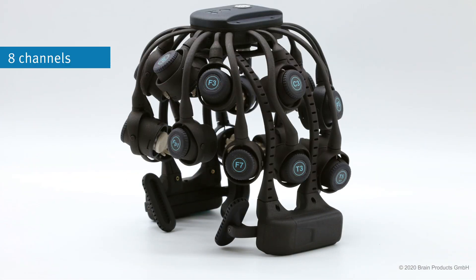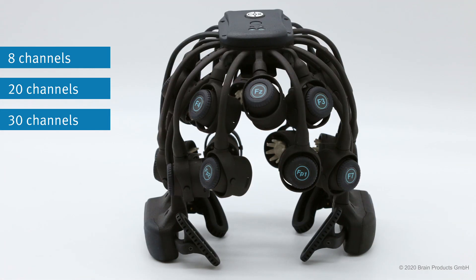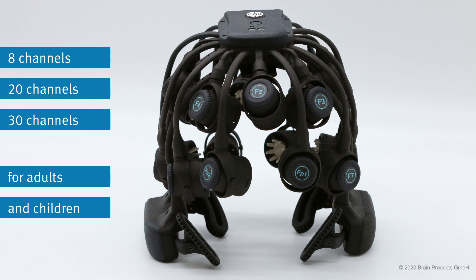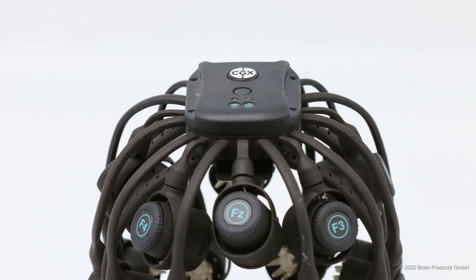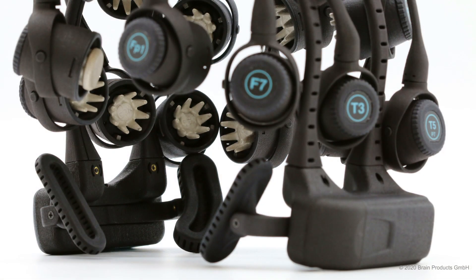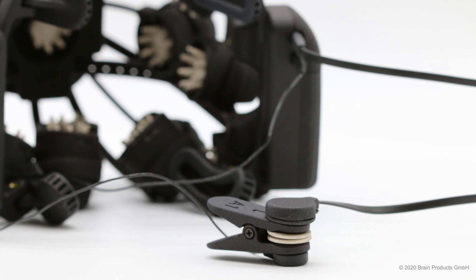The Quick headset comes in 8, 20, or 30 channel configurations and follows the one-size-fits-all concept with versions for adults and children. The headset already contains all you need to get started with your recording: a wireless amplifier, a series of legs with active dry electrodes, and a base structure containing earpads, the battery compartment, and the input for ground and reference ear clips.